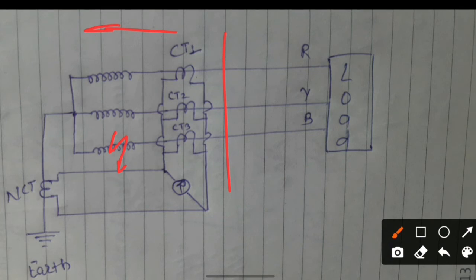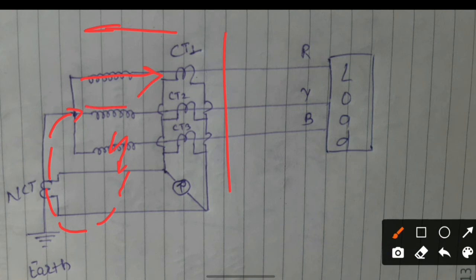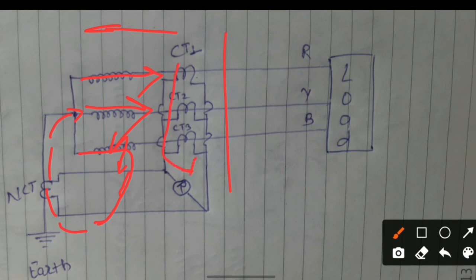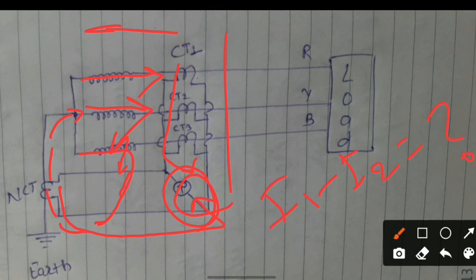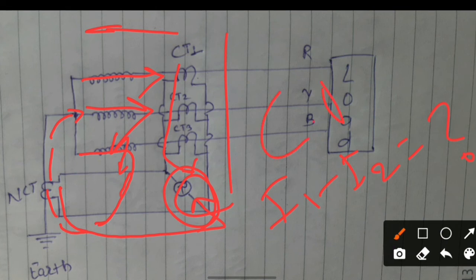If the fault occurred inside the protection zone — let's say on the B phase — the fault current flows through the winding. There is some current in CT1 on the R phase and some current in the Y phase, but there is no current in the B phase CT, so unbalanced current flows. This current flows one way, and the NCT senses the fault current flowing the other way. At this time I1 minus I2 equals something non-zero. The relay will operate on an internal fault, sending a command from the relay to the circuit breaker, and the CB will isolate the transformer from the generator.